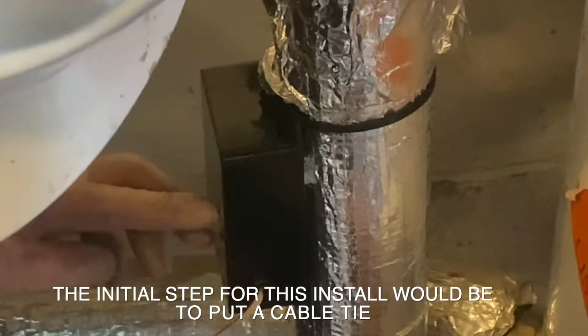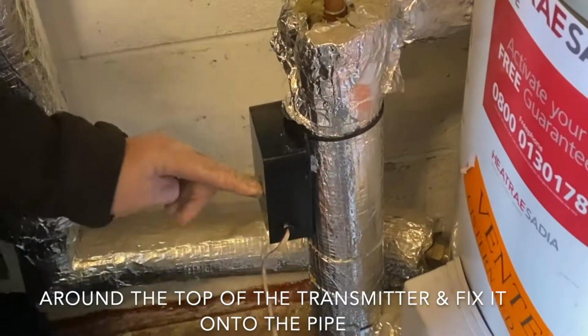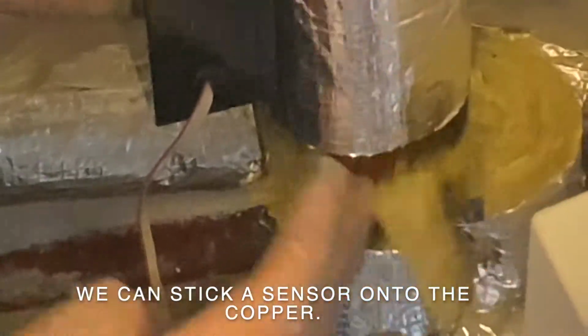So the initial step for this install would be to put a cable tie around the top of the transmitter and obviously fix it onto the pipe. Leave the bottom cable tie for the moment and then cut the pipe insulation so that we can stick a sensor onto the copper.